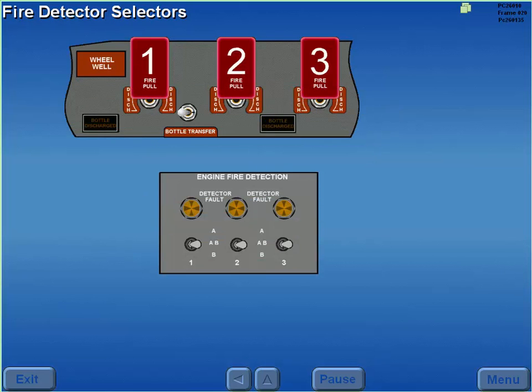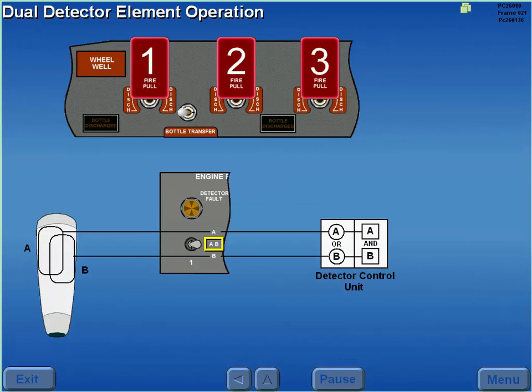The selection of each engine's A and B detector elements is controlled by the respective fire detector selector. With the selector in the normal A-B position, concurrent signals from both detector elements are required to initiate a fire warning.